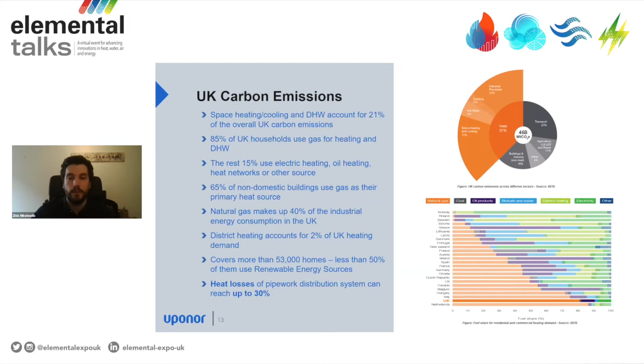Looking more into detail on heat networks, district heating is the concept of having one or more central heat sources instead of individual boilers. The heat is transported from the central heat source through a network of underground pre-insulated pipes to each building. Each building typically uses heat interface units or some sort of central heat exchanger, which provides space heating and hot water to the building from the district heating network.